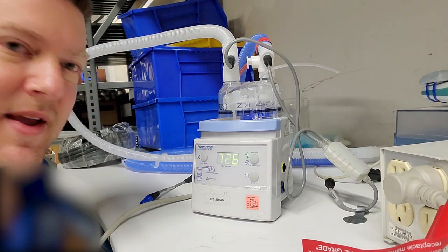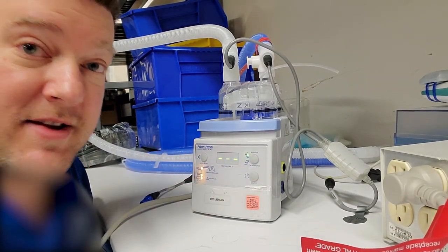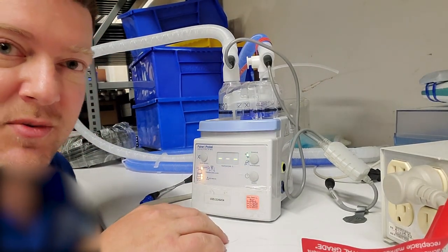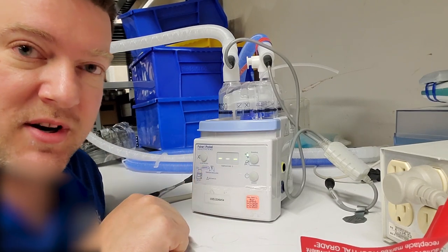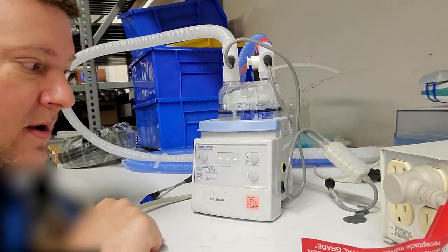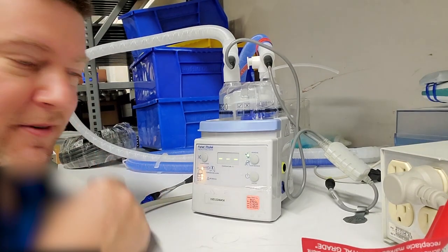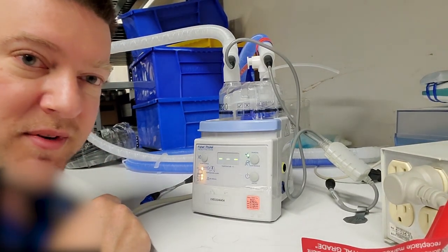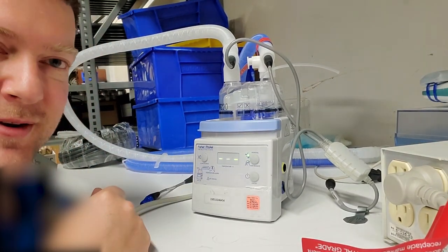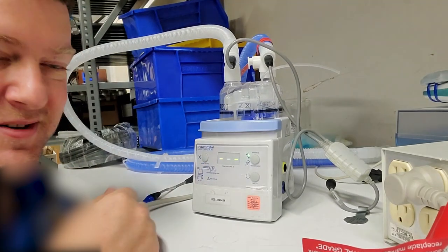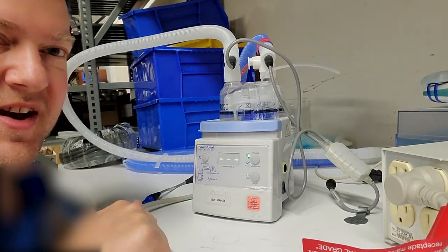And then it goes to 'end' and then it will power itself off. There it goes, now it goes into regular functionality. All right guys, so that is the Fisher and Paykel humidifier, just a simple temperature calibration check. Let me know what you guys think. It's a very simple device; we see them throughout the whole entire facility, but we got to do little checks every single year. So here we are, thanks for watching guys.